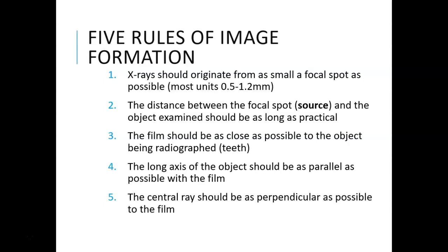And it's a half a millimeter to just a little over 1 millimeter. It's very small. The distance, the second rule, the distance between the focal spot or the source and the object examined should be as long as practical.